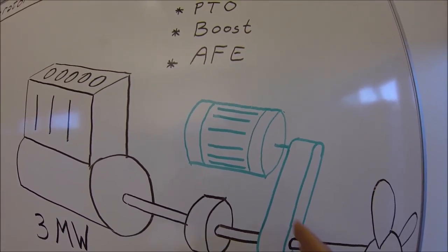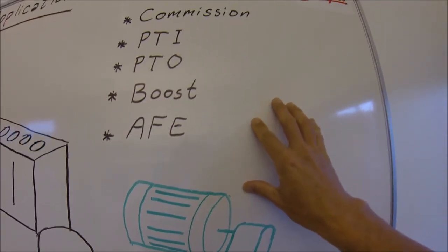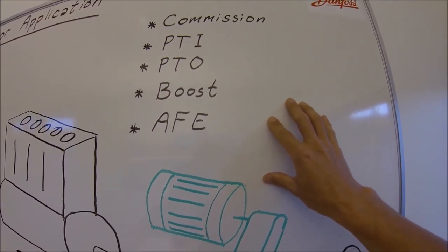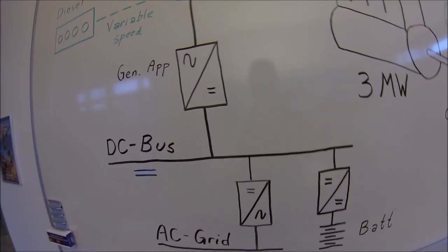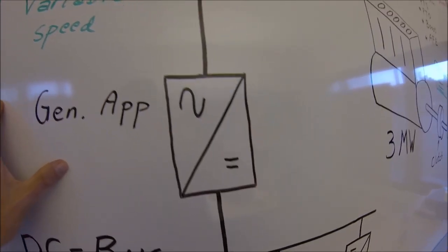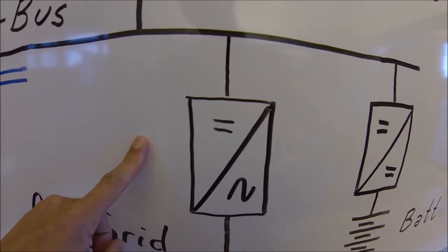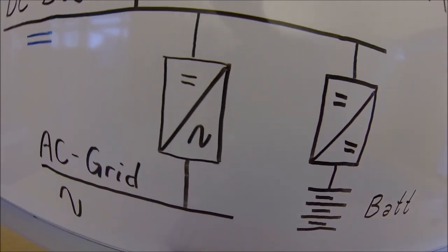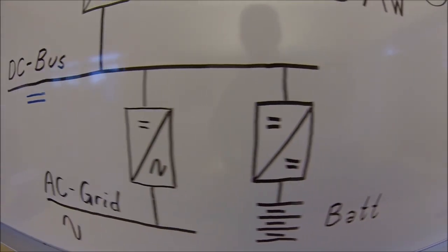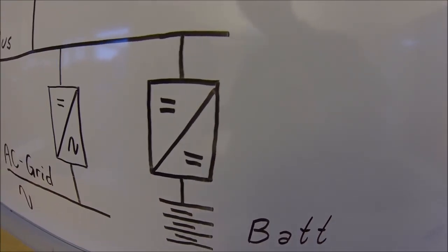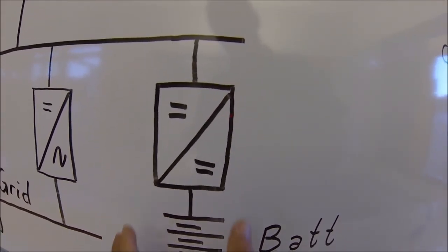Since energy can flow in both directions through the system, the generator application needs to be supported by a DC bus system which also is bi-directional. Typically the generator application is connected to an active frontend or microgrid application which is connected to the ship AC grid. It can also be connected to energy storage, typically a DC to DC converter and a battery.